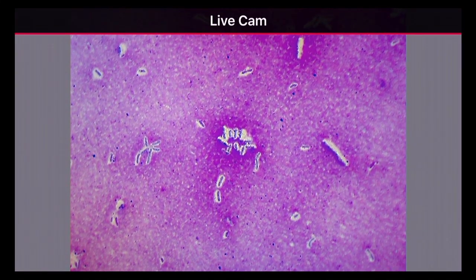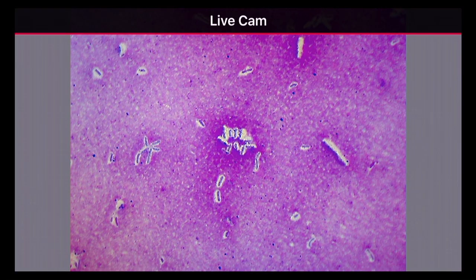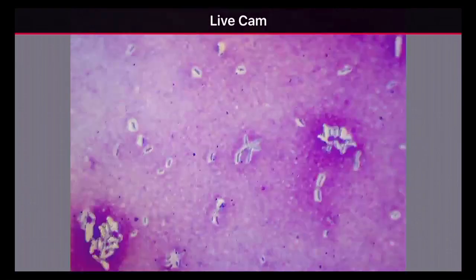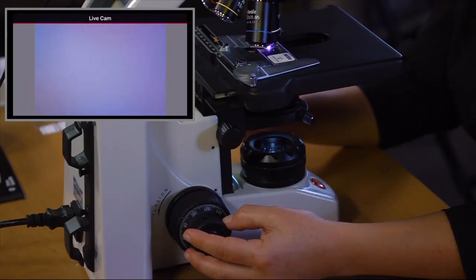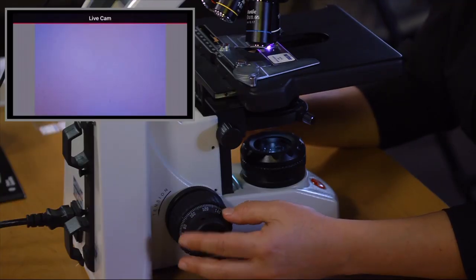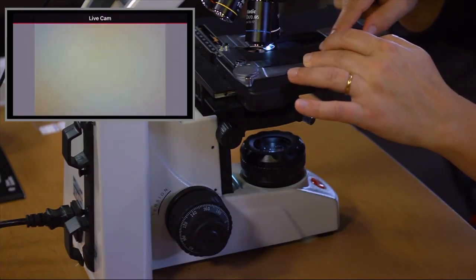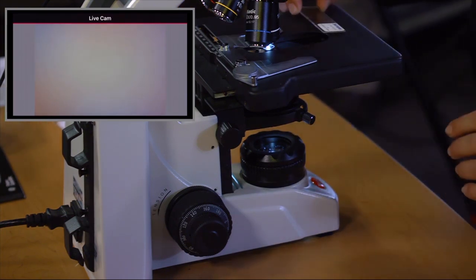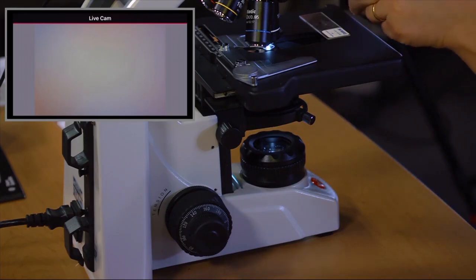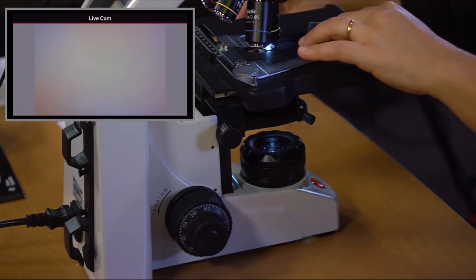In the beginning it will be a little bit difficult for you to use the oil immersion, and one trick is to always move the fine focus and the stage knob at the same time, so you know when you come into focus because your image in the microscope moves. It takes a little while to become good at it. To change the slide from the oil immersion, you can just remove the slide, use another slide, add a little bit of oil to your specimen, and slide it right back into your clip.